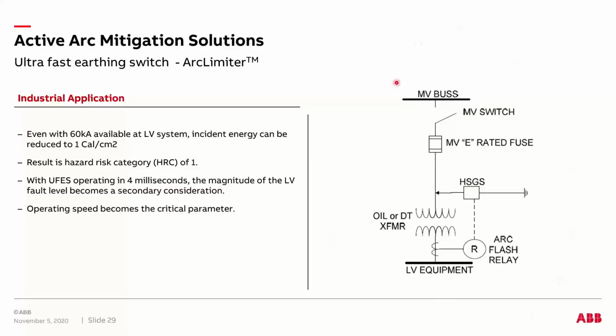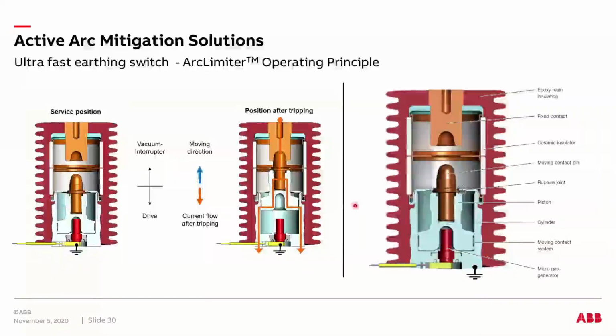And we have actually performed KEMA testing for this particular setup, and we were able to measure the incident energy to be less than 1 calorie per centimeter square on the low voltage side of the equipment. And yes, the fault has been cleared in less than 4 milliseconds in this particular scenario. The UFES element itself, we call it the primary switching element, and this is the cutout of one of the elements. So we have 3 elements connected.